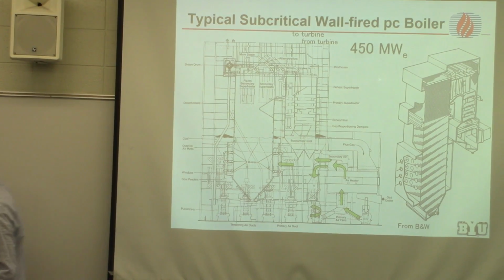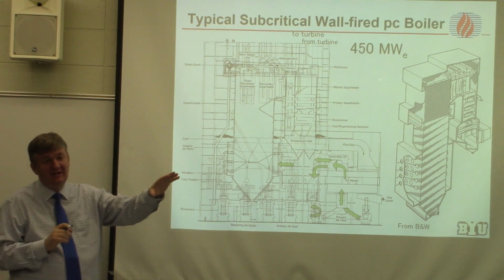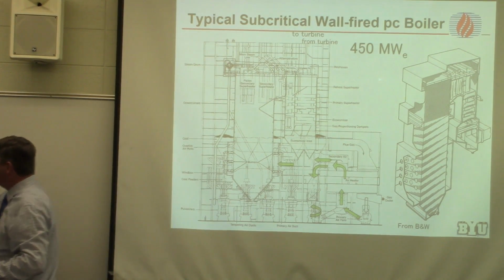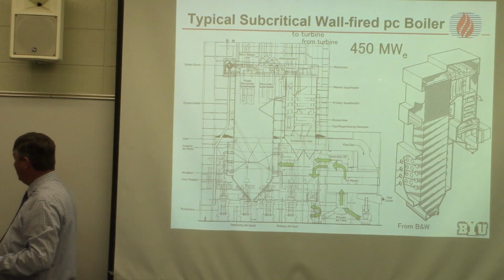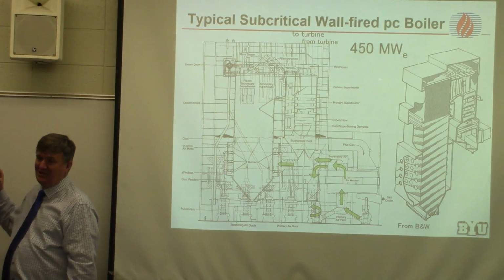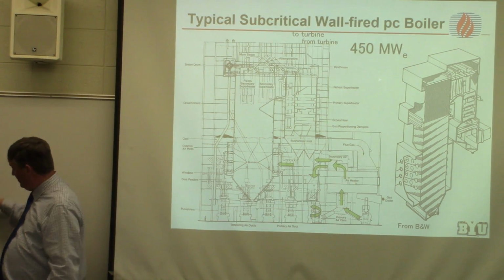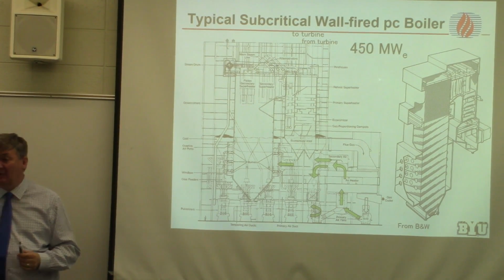So you get a nice, stable flame that sits right out in front of this burner instead of it going—if you didn't circulate this air like this, the coal would just sail right across the boiler and smack into the wall on the other side, and that would not be good. Then it would dribble down the wall and out the bottom, which would be really bad.